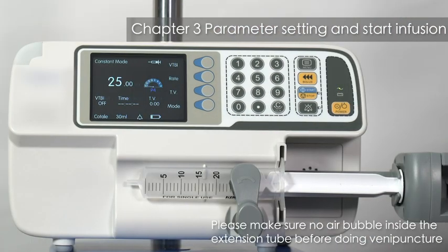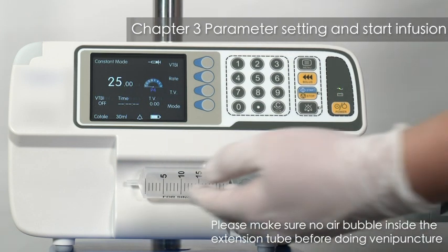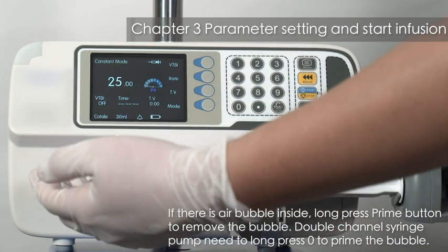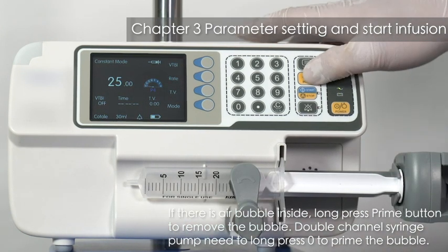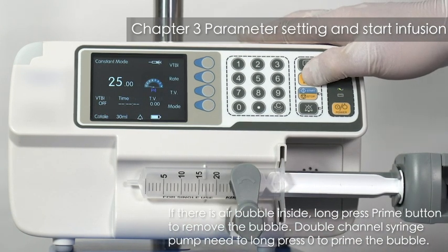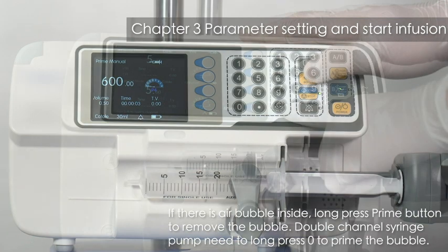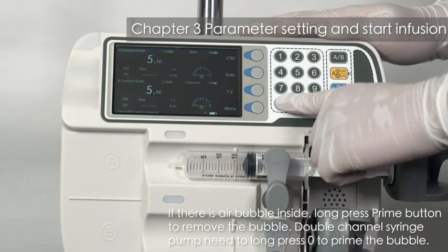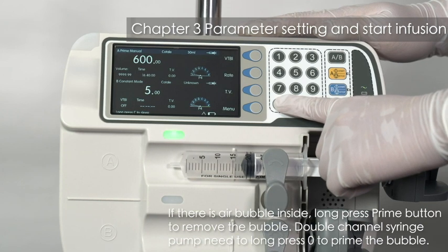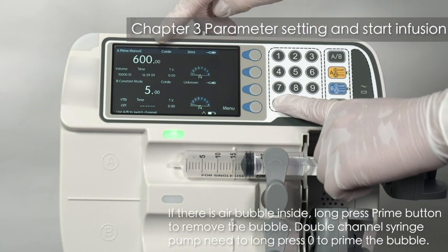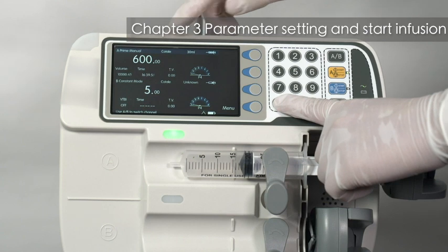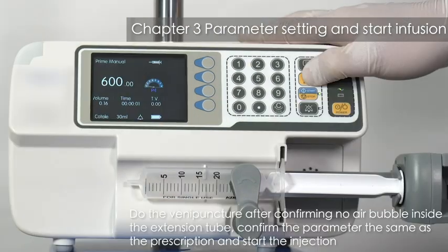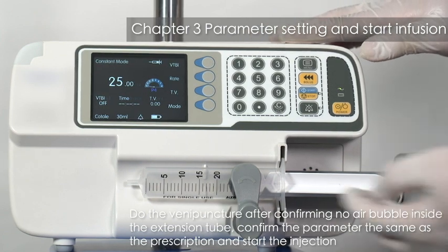Please make sure no air bubble inside the extension tube before doing venipuncture. If there is air bubble inside, long press Prime button to remove the bubble. The double channel syringe pump needs long press 0 to prime the bubble. Do the venipuncture after confirming no air bubble inside the extension tube.